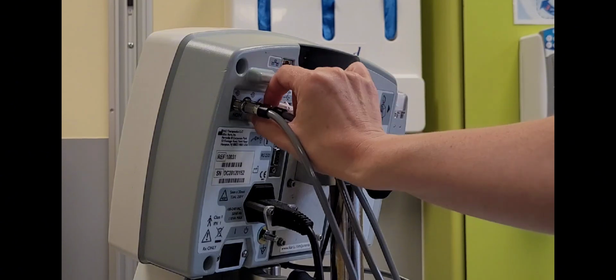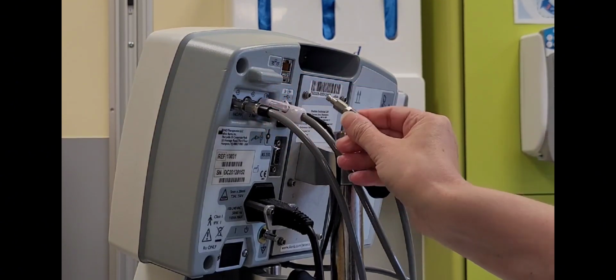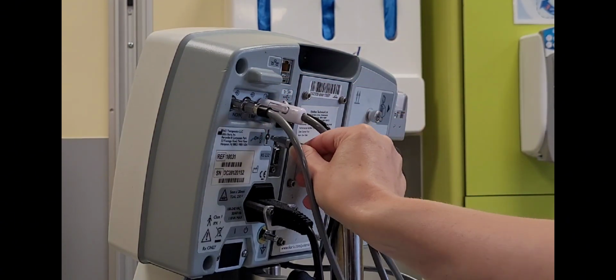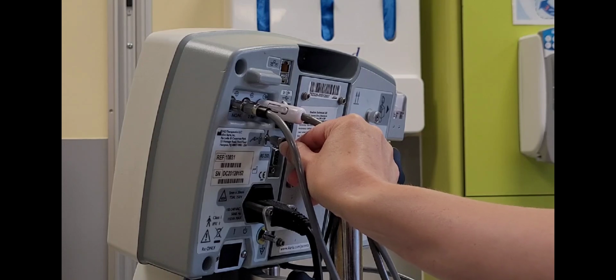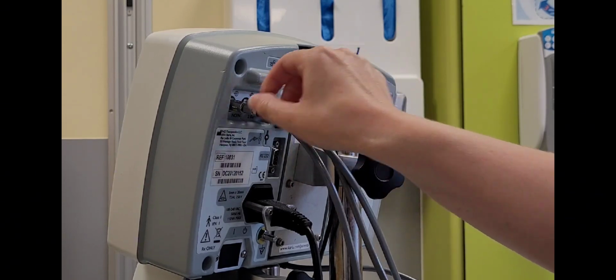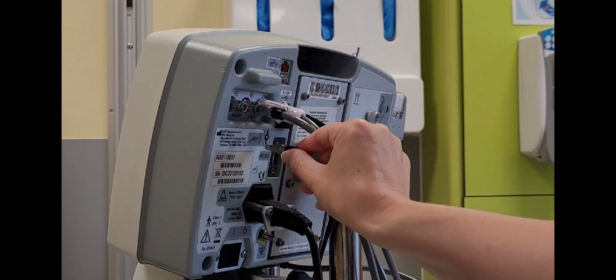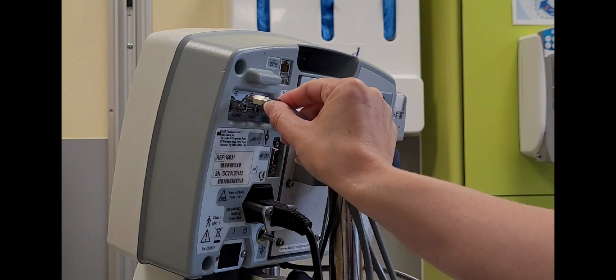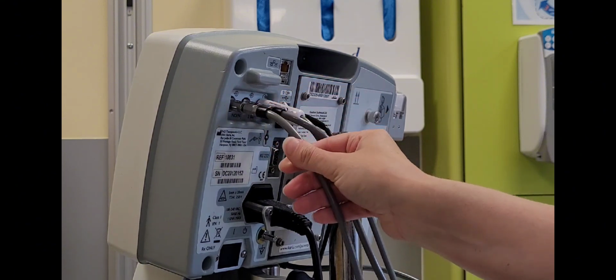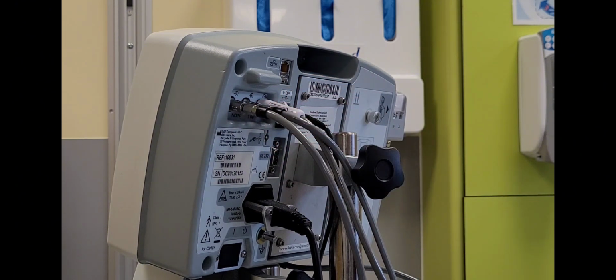The final step in the process is to purge the lines. Disconnect both gas lines and insert them into the purging port. All the remaining gas in the lines will be discharged. Once the hissing stops, reconnect the gas tubes. It is important that the cylinders are off when this is carried out, else you'll be emptying the cylinders, not just the line.